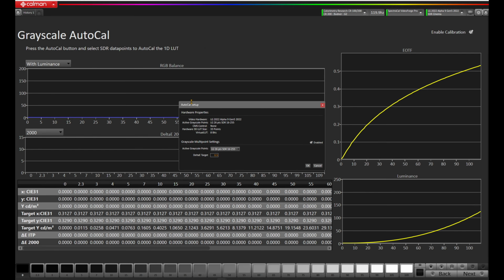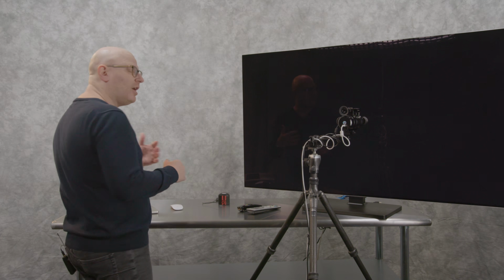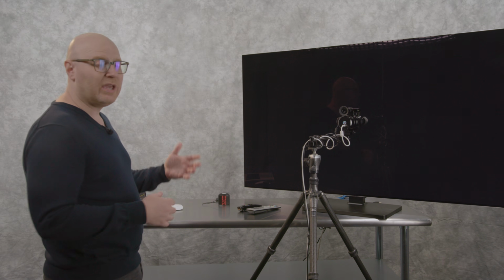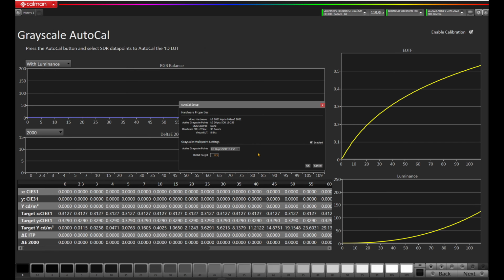Okay, so you've seen the auto cal setup window come up, and you'll notice that we have active grayscale points we can select from. Calman has run through a couple test images, and it knows that the range is 16 to 255. As such, the default value here came up with LG 26 points, SDR 16 to 255. That accounts for super white information.